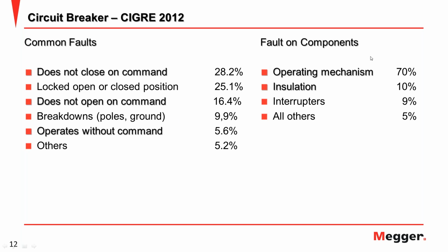And for components, the operating mechanism gives you a high percentage, 70% compared to others like insulation or interrupter faults. So based on this information, I think we need to do breaker maintenance, MV breaker maintenance, correctly.